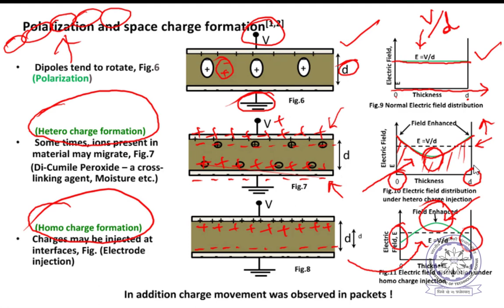So this forced us to investigate actually. What are the possible effects of this electric field distortion? We can have a look here. There may be local electrical overstressing, that's what we have seen, where somewhere the electric field is high. This may result in local degradation and breakdown of the insulation. Another is the accelerated aging effect. Normal electric field aging is at a normal rate, but if the electric field is over and above the average field, there will be accelerated aging, and the life of the insulation gets reduced in this process.